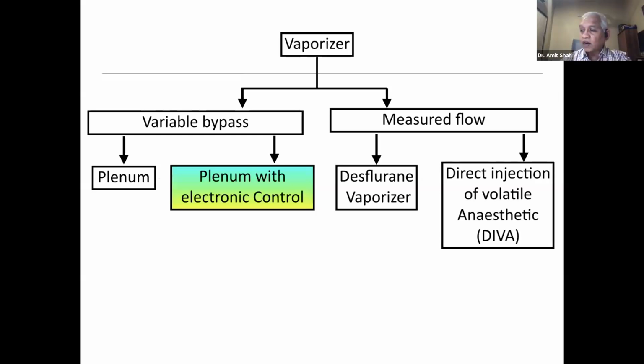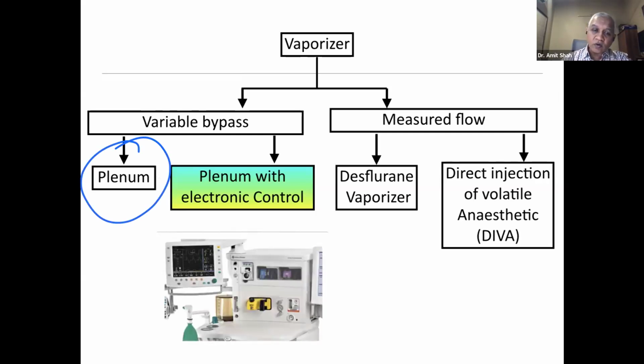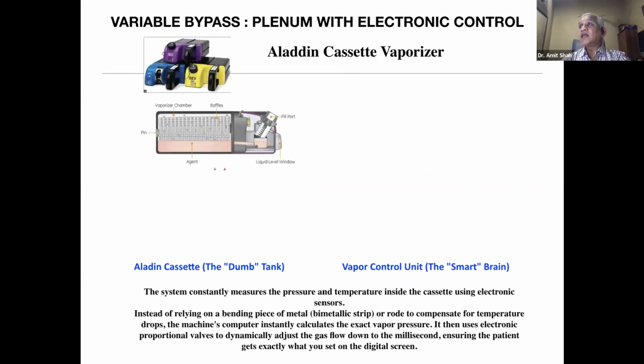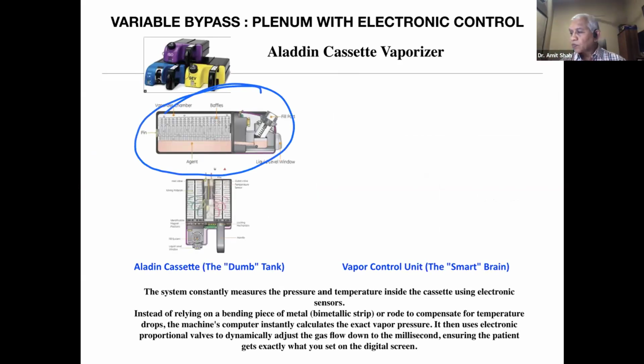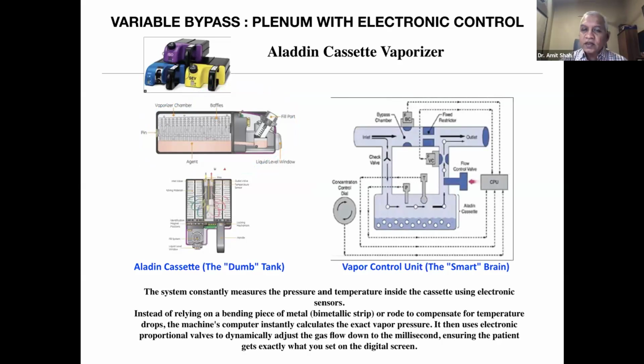So we have seen first the plenum one. Now we'll see plenum with the electronic control. So which are the electronic controls? If anyone has heard of the Aladdin cassette vaporizer, which is part of one anesthesia machine. So the Aladdin cassette has two things. One is the cassette, a dumb cassette. That means in this cassette, they get the liquid. And then there is a control unit. This is the liquid tank, and then this is a control unit. Now, how is it different? It is a variable bypass, that is for sure. So this is a variable bypass vaporizer.